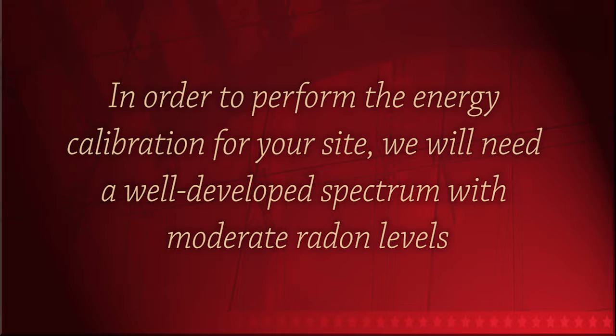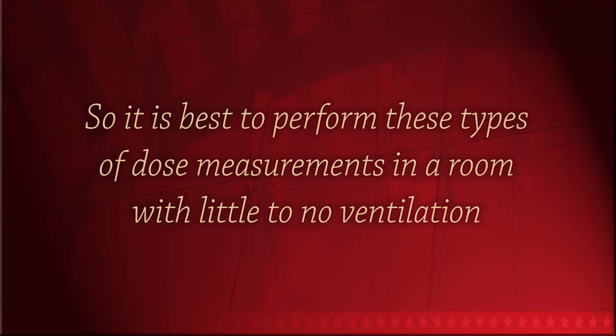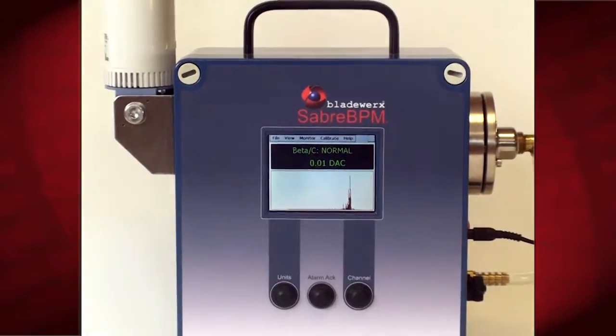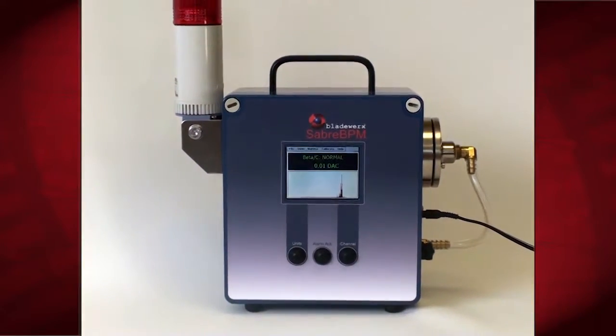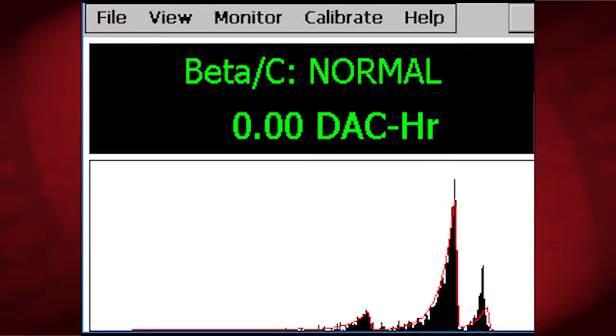In order to perform the energy calibrations for your site, we will need a well-developed spectrum with moderate radon levels, so it is best to perform these types of dose measurements in a room with little to no ventilation. Now, leave the BPM running to measure for several hours. This usually takes place overnight.